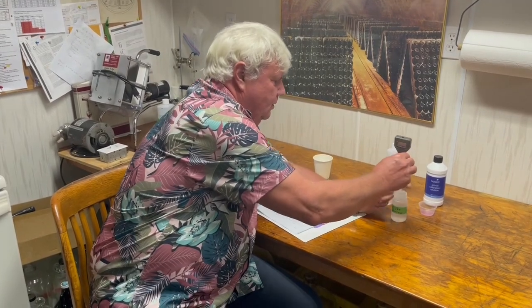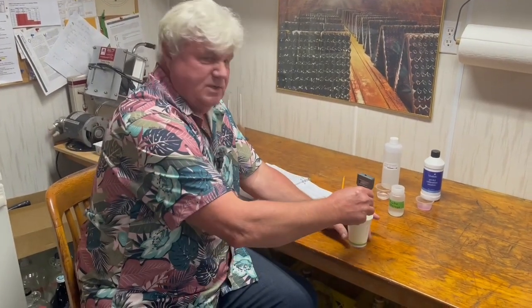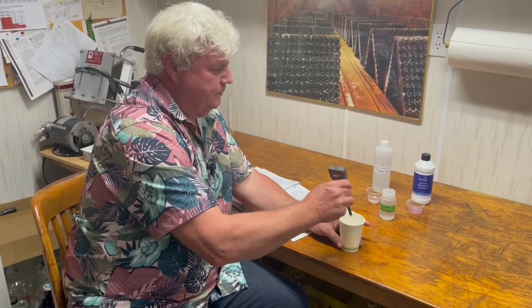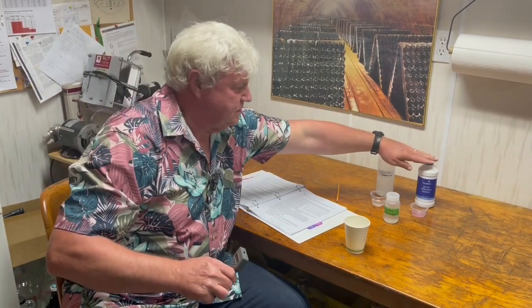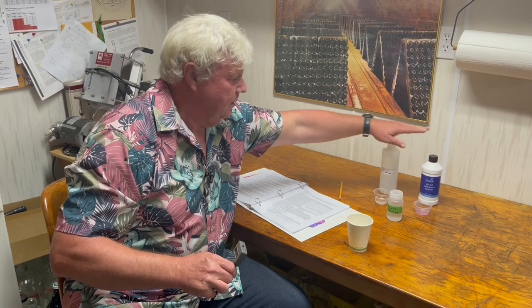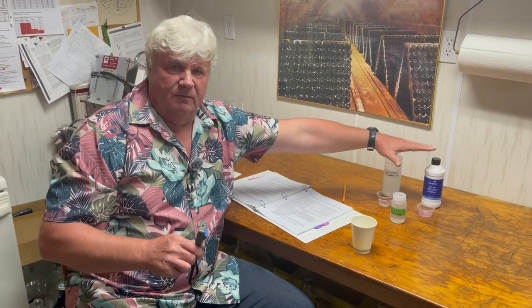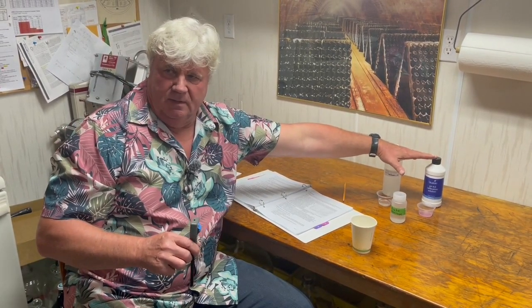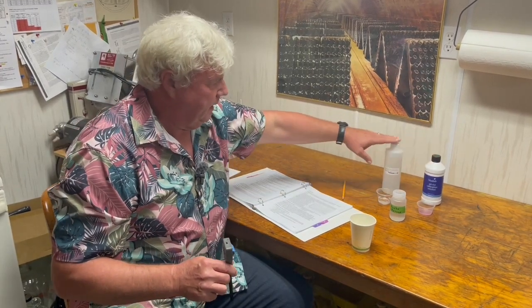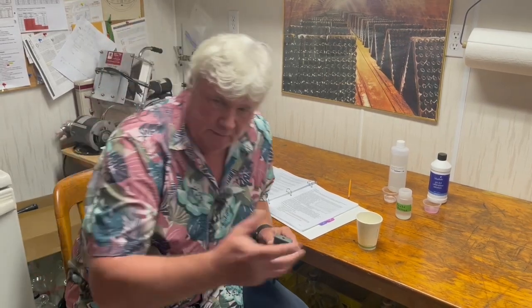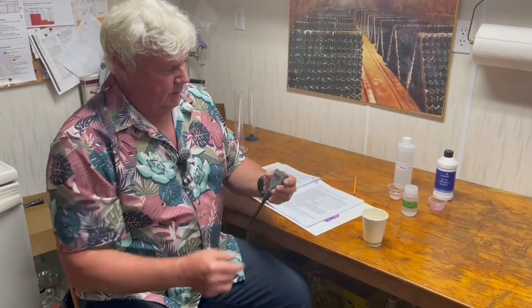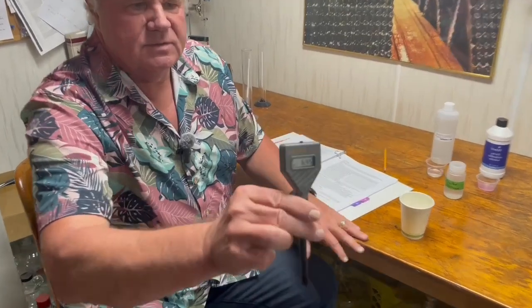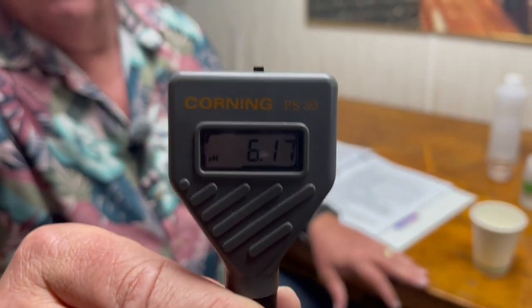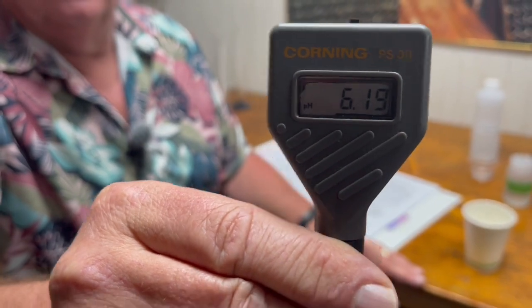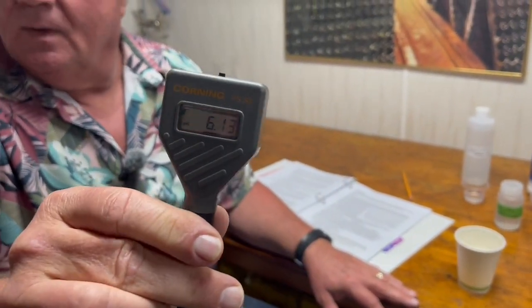So I'm just going to go through it. Whenever you pull it out of that solution, this is distilled water, so you rinse it in distilled water. There are 2 different calibration solutions: a pH of 4 and a pH of 7. Sometimes they'll have a pH buffer solution of 3. But this one I've got 4 and 7 because that's what this pen needs. And it'll tell you on the top what it needs, or in the instructions. So you turn this on. If you get close, you can see the display there. That is reading 6.1. That's just from the water.